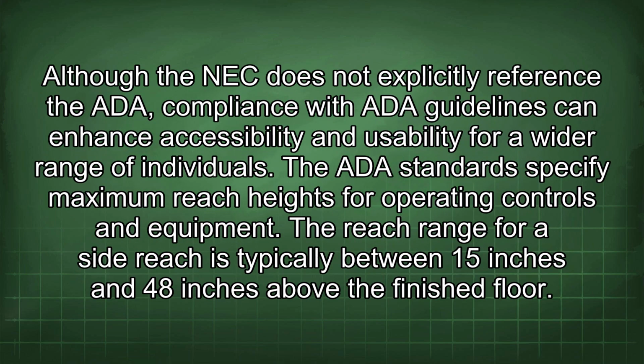Although the NEC does not explicitly reference the ADA, compliance with ADA guidelines can enhance accessibility and usability for a wider range of individuals. The ADA standards specify maximum reach heights for operating controls and equipment. The reach range for a side reach is typically between 15 inches and 48 inches above the finished floor.